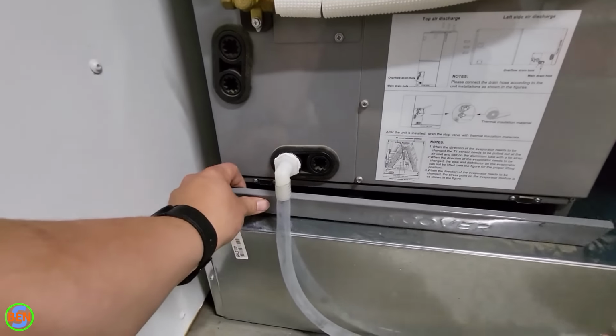So before we start the system, you want to just go down the list of things that were involved in your installation, like the wiring, all the ductwork, the line sets, making sure that all the fittings are properly tightened, making sure that the valves were all opened properly after you pulled your vacuum, and all the condensate drains are ready to go. Then you are ready to finally go ahead and start up the system.